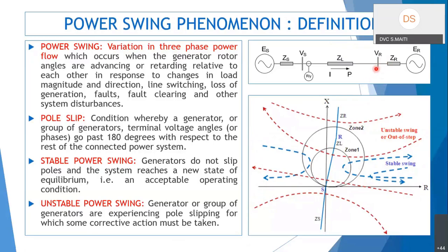The original load point might be in the negative R axis region. If current flows from S to R and we plot the impedance seen by the relay in the R-X plane, it will be in the positive R zone. For an unstable swing, the impedance crosses from right to left or left to right — that is the swing.